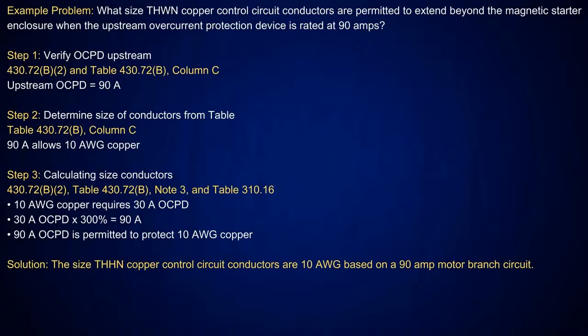Now, this is where you're permitted to extend beyond the magnetic starter. So that means it's not inside an enclosure. In other words, I'm running a conduit over to it. It's some type of raceway. And you'll see it says upstream overcurrent device protected be 90 amps. Well, if you go over and look, it's going to tell you in table 430.72(B) column C. So now I'm in column C instead of B. And it's going to tell you 90 amp allows a number 10.